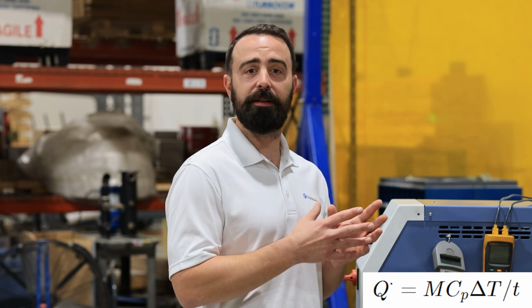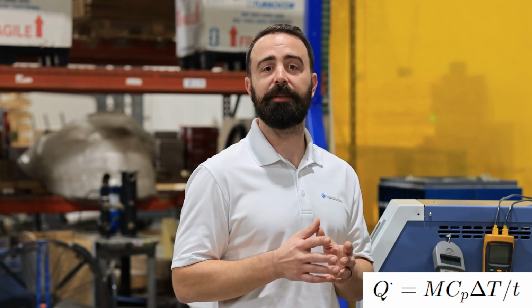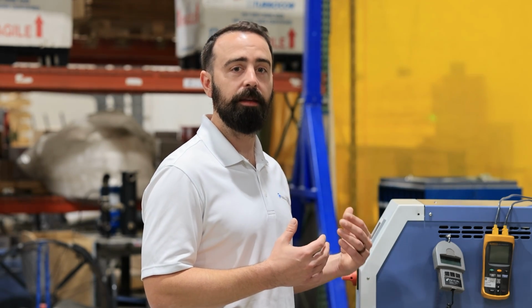The thermodynamic basis of the weighed water test is an equation Q equals MC delta T, where Q is the energy transferred, M is the mass, C is the specific heat of the material, and delta T is the temperature change. What we do in order to get that mass component is we determine a flow rate and then use the density of the fluid, typically water, to convert that to a mass.